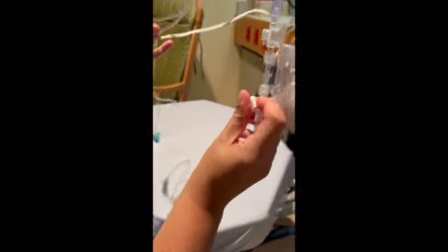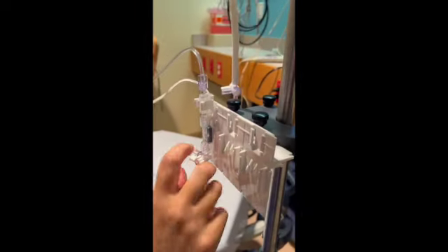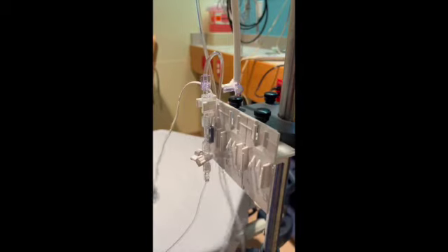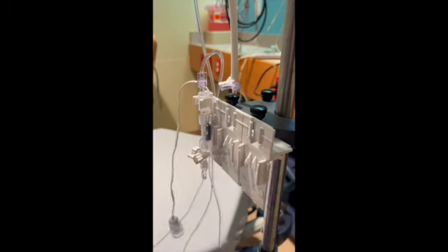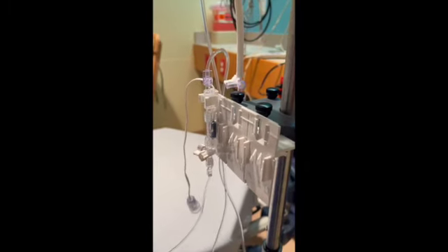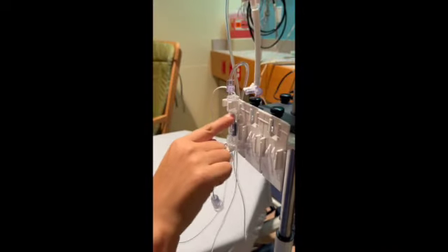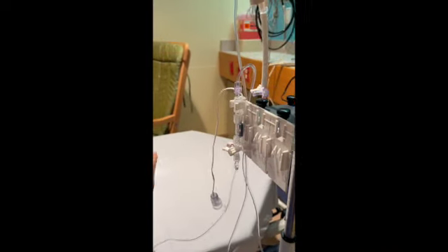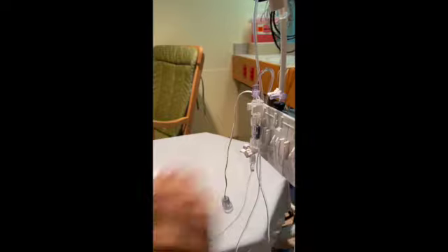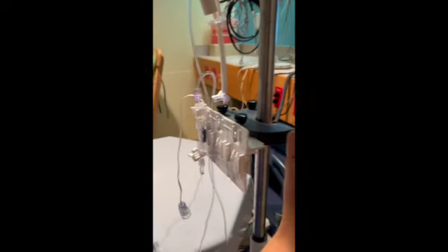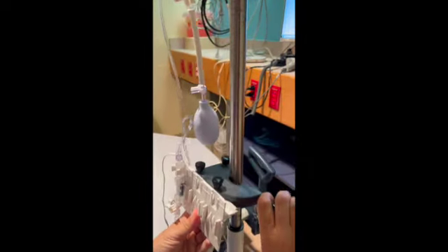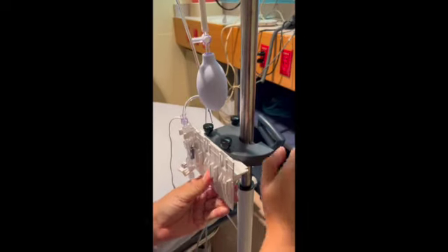In some cases, the transducer can come out on one of these mounting plates. The only change in that would be that your stretcher needs to be pulled up so that the monitor transducer part is still at the mid-axillary line at the level of the heart. That can be the stretcher coming up and/or the mounting plate coming down so that you end up exactly where you should be.